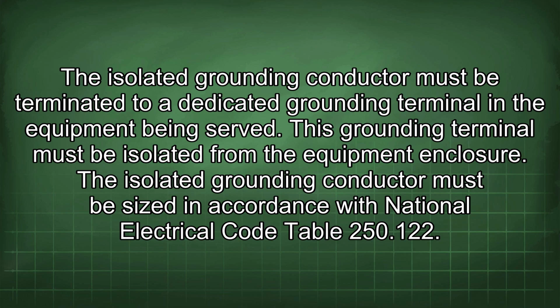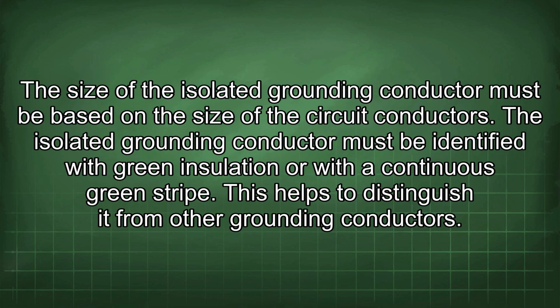The isolated grounding conductor must be sized in accordance with National Electrical Code Table 250.122. The size of the isolated grounding conductor must be based on the size of the circuit conductors. The isolated grounding conductor must be identified with green insulation or with a continuous green stripe. This helps to distinguish it from other grounding conductors.